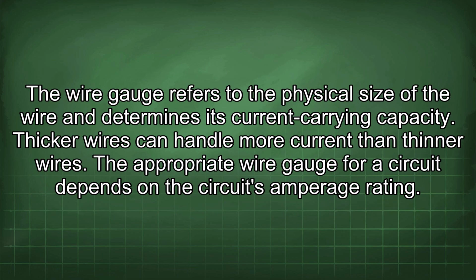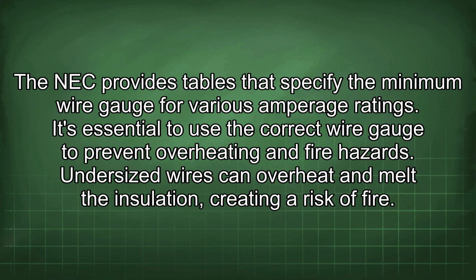The wire gauge refers to the physical size of the wire and determines its current carrying capacity. Thicker wires can handle more current than thinner wires. The appropriate wire gauge for a circuit depends on the circuit's amperage rating. The NEC provides tables that specify the minimum wire gauge for various amperage ratings. It's essential to use the correct wire gauge to prevent overheating and fire hazards. Undersized wires can overheat and melt the insulation, creating a risk of fire.